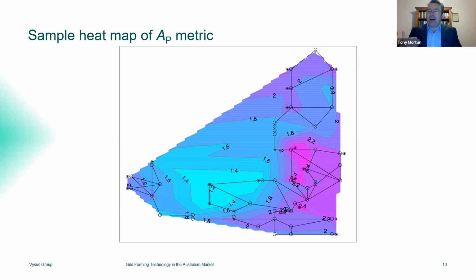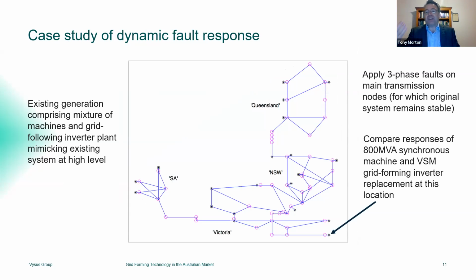But this by itself isn't enough. This does give us some very useful metrics, just like short circuit levels and short circuit ratios do. But it's also important that we back that up by understanding the actual dynamic stability behaviour of these different technologies. And so just showing a typical case study, we've taken one of the large generators in the Australian system, and we've pulled that out and we've replaced it with an 800 megawatt grid forming BESS using a fairly generic model to study the dynamics of that, just to see how it affects the stability behaviour of the system overall.